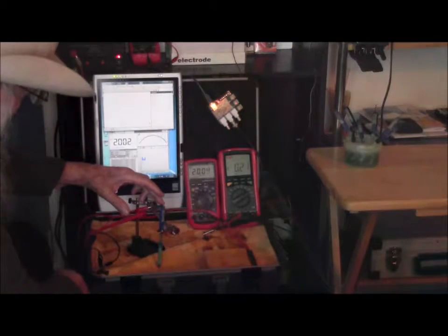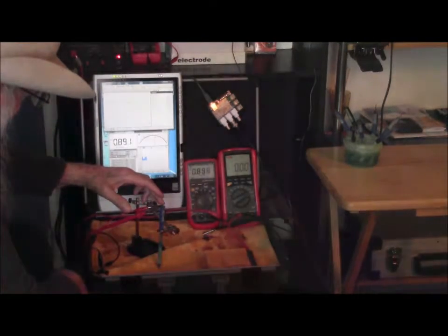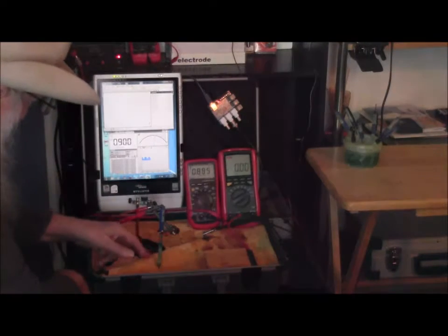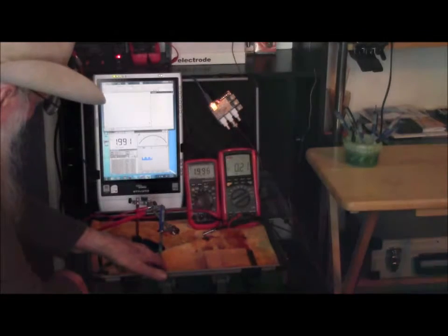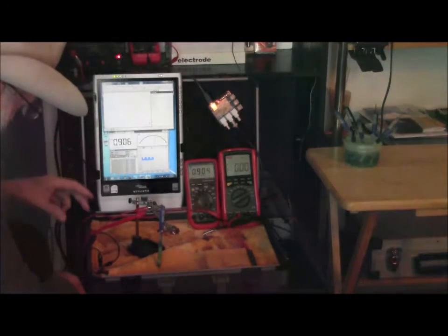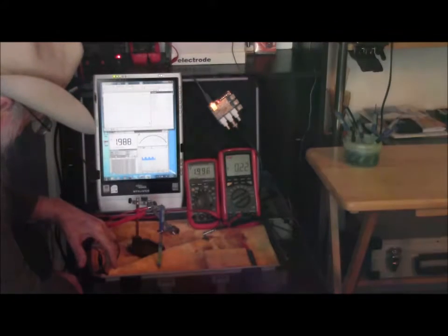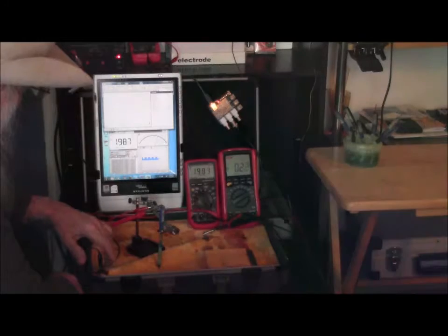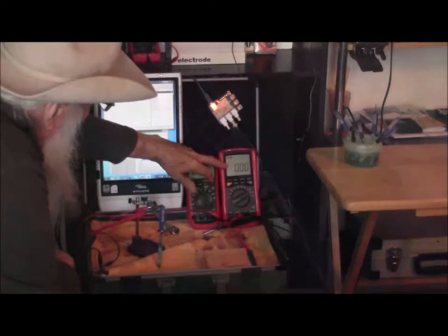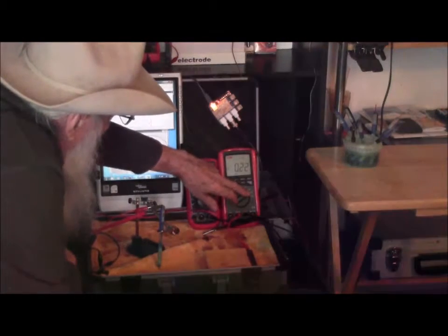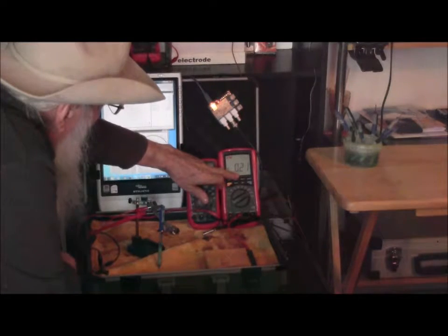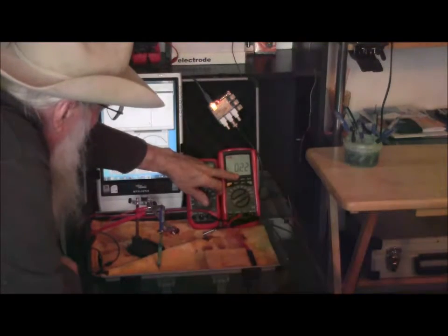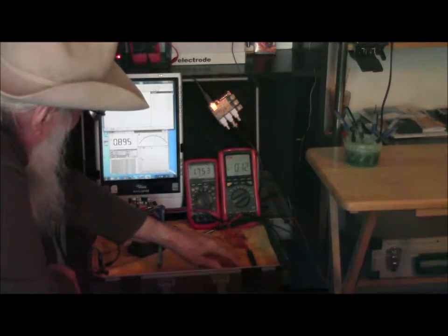This is measuring the pipe to soil potential differences between the contact point here in the electrolyte and the negative connection, which is to the pipeline metal itself. This meter is set on milliamps and is showing the switching from 0 to 0.22 milliamps, which is the current going through the ground bed.